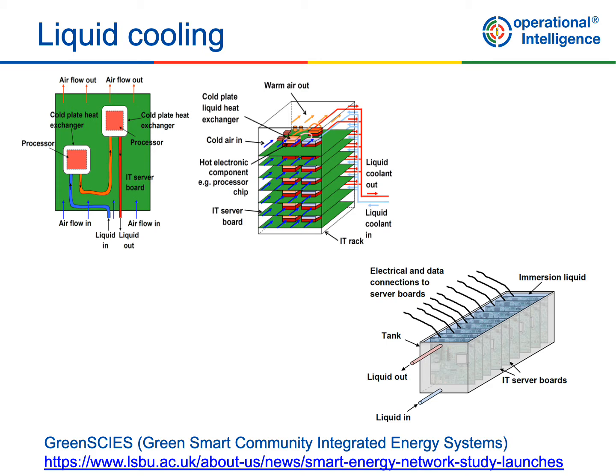This increasing densification is leading to a growth in liquid cooling, a trend which we see continuing. There are different types of liquid cooling. The slide shows a couple of options. On the top left, we have liquid on-chip cooling, where a fluid, usually water, is piped to and from the highest heat load components on the printed circuit boards, and we have a heat exchange via a cold plate. This is supplemented with air cooling for the other components. An alternative to this is immersion cooling, where the hardware is suspended in fluid, such as an oil, to remove the heat. These types of cooling potentially allow higher grade heat to be recovered, which makes heat reuse more viable.